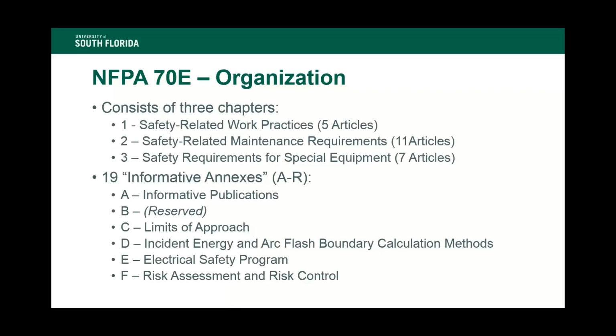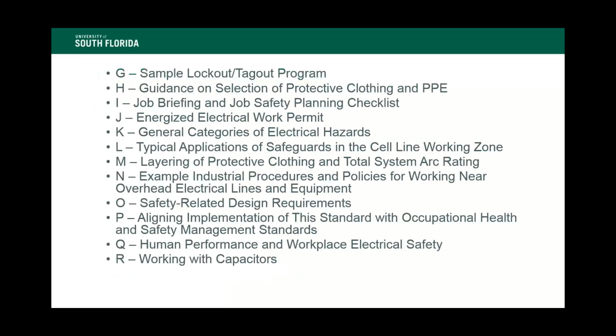There's additional information spelled out in 19 informative annexes, provided after the standard itself. These annexes provide information on everything from reference publications for more information, a discussion on limits of approach, a sample electrical safety program, and a discussion on risk assessment and risk control. Also, in Annex D, there's a means of calculating incident energy and arc flash boundary for different situations, and we'll talk about that more shortly.